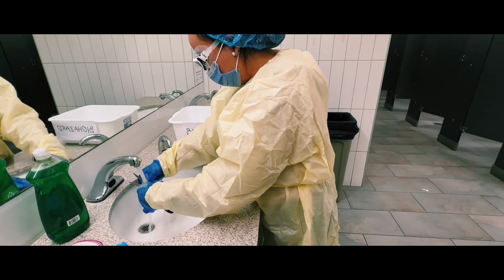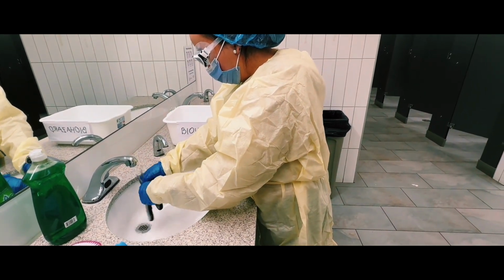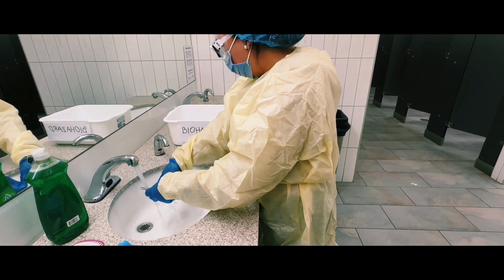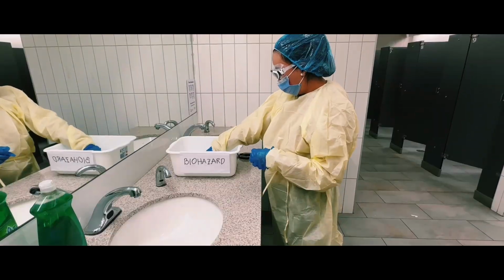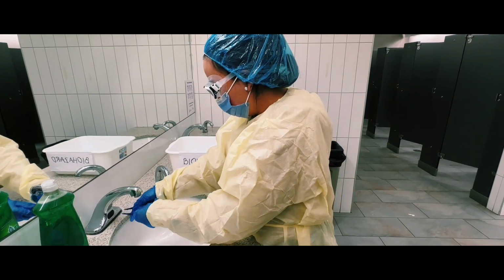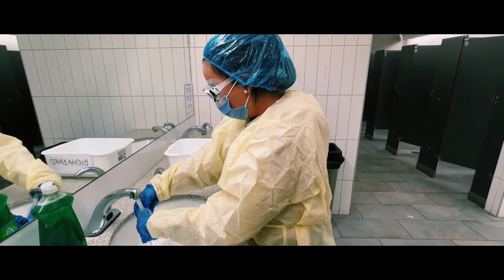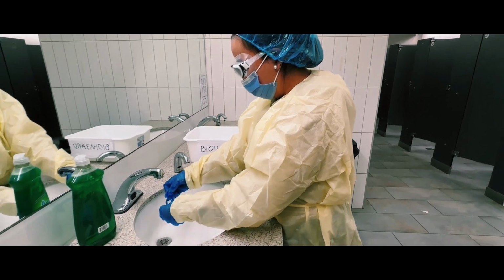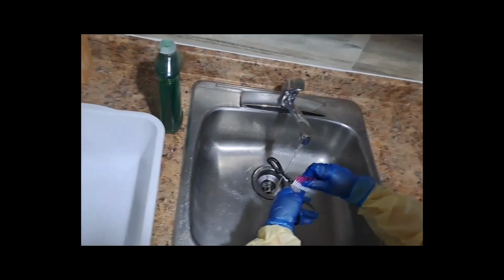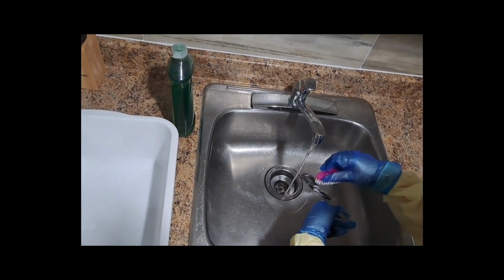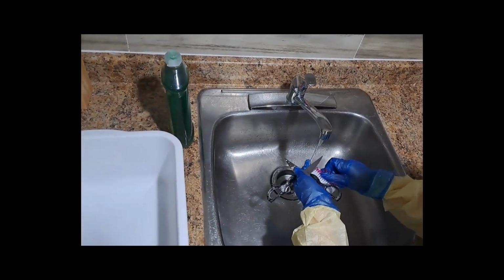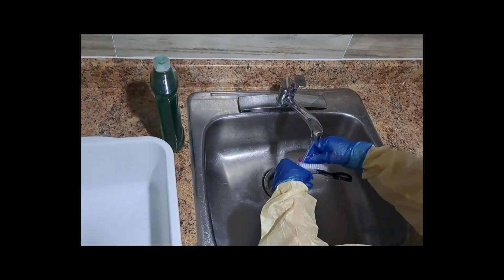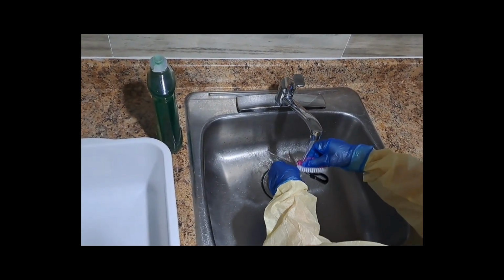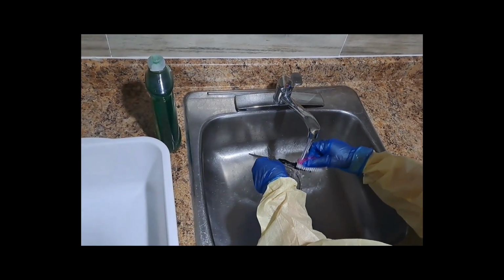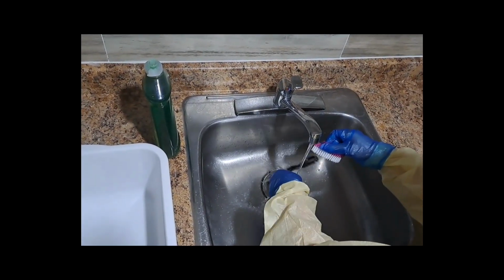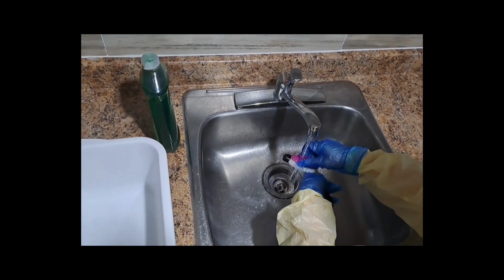Rinse the instruments in cool water and place them in a disinfectant solution to remove any blood or debris that might dry onto the instruments. Scrub the instrument well with detergent and water. Ensure to include inside edges, serrations, grooves, hinges, and all surfaces. Scrub under running water. Ensure all debris has been removed prior to sterilization.